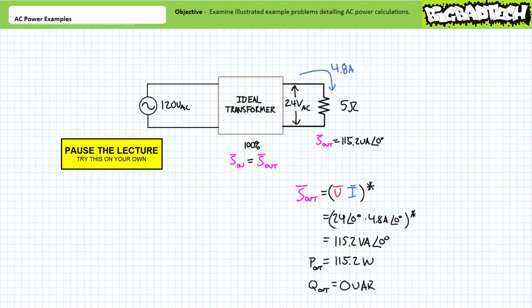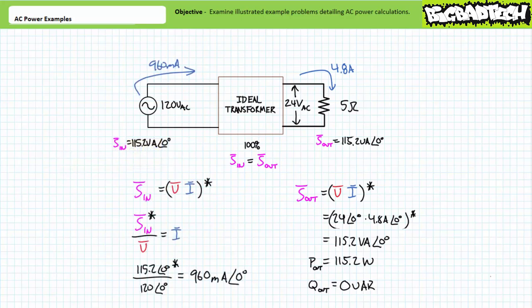If you're tracking, you should have come up with the following results. If the transformer was truly 100% efficient, power in should equal power out. Given power output has been calculated to be 115.2 volt amperes at an angle of 0 degrees, one might expect power input for a 100% efficient device to also be 115.2 volt amperes at an angle of 0 degrees.